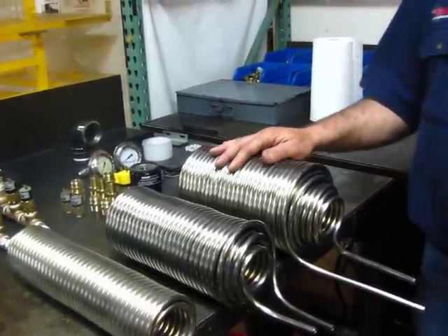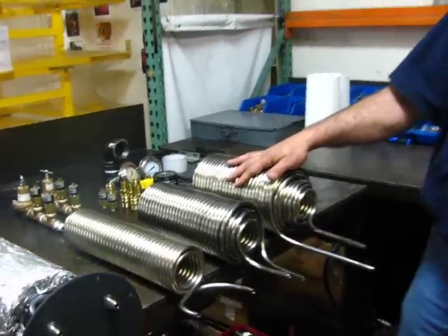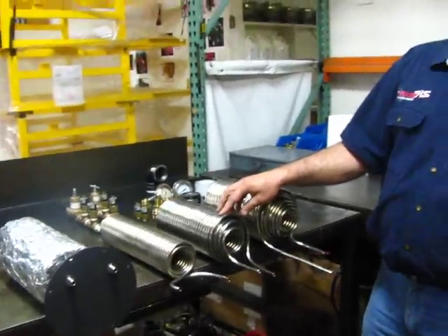Now, the most popular one that we build is the one with 4 layers, because when you're dealing with a coil system and pressure from the pump enters it, per every 100 feet of coil—depending on the diameter—you do have pressure loss. For example, in the 3/8 size, per every 100 feet of coil you lose 40 psi.